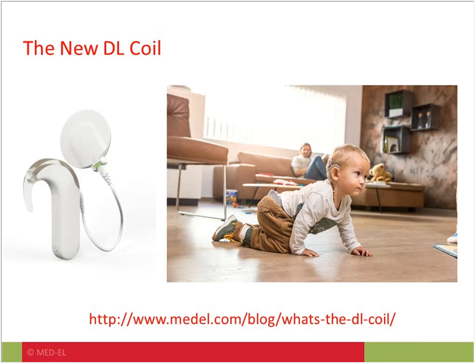Problems could mean that a cable is broken, the coil is disconnected from the implant, or for bilateral children, that the coil is on the wrong side of the head. After 5 minutes, the coil will totally shut off to save power, and the red light will only blink once every 10 seconds instead of once every second until the battery dies.